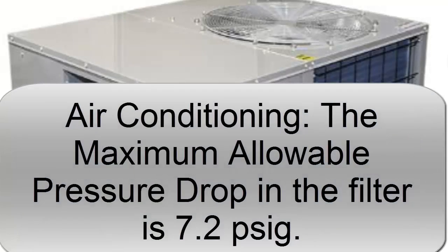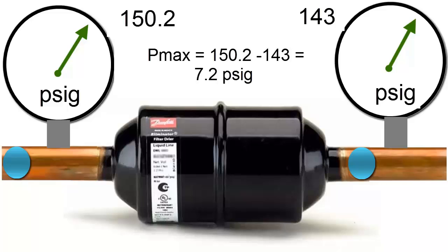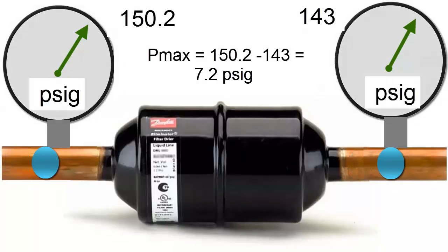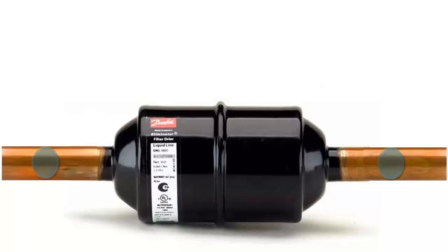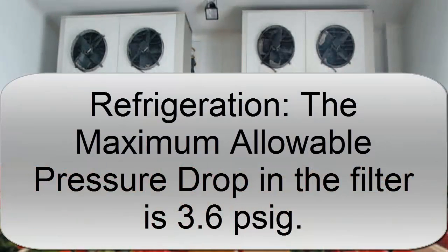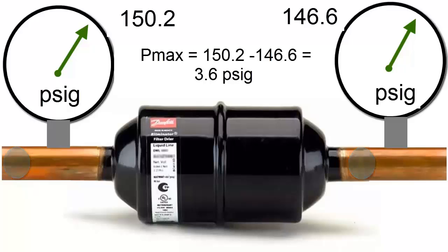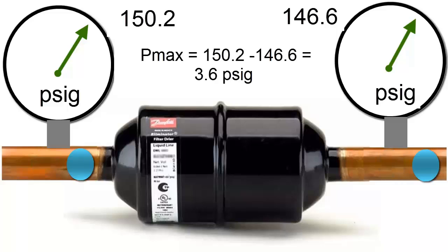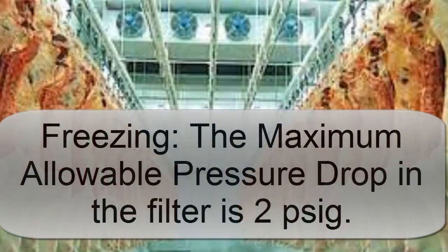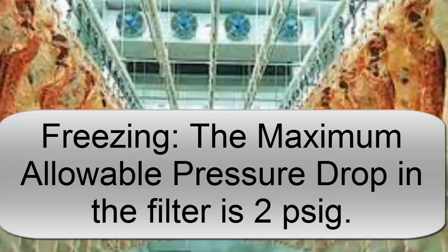In air conditioning systems, the refrigerant pressure drop indicating a clogged filter is 7.2 pounds per square inch. In refrigeration systems, the pressure drop suggesting a clogged filter is 3.6 pounds per square inch. In freezing systems, the pressure drop signaling a clogged filter is 2 pounds per square inch.